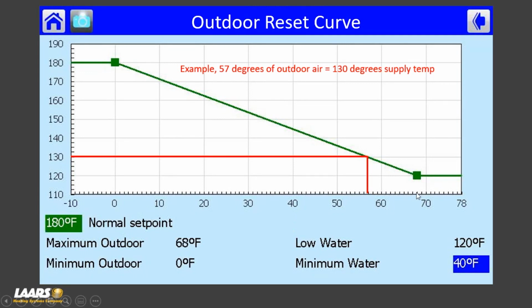Now, the other thing I forgot to mention, this is not your warm weather shutdown. Your maximum outdoor temperature is the maximum for your heating curve. Warm weather shutdown, in this example, always keep it a couple of degrees above your high point, or your maximum outdoor temperature. In that example, I might choose 70 degrees. So at 70 degrees, or if it's 72 out and someone turns on a thermostat, the heat won't come on. If you have a combi boiler, absolutely it'll run for domestic, but your heating system will not.